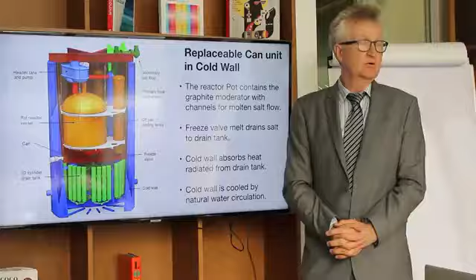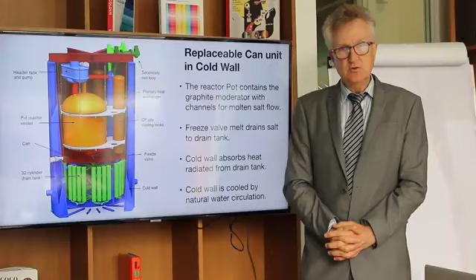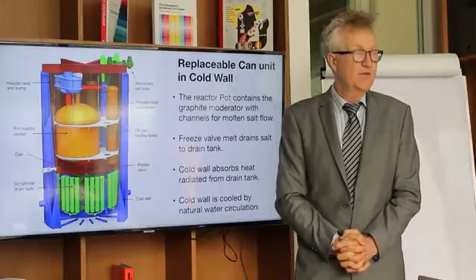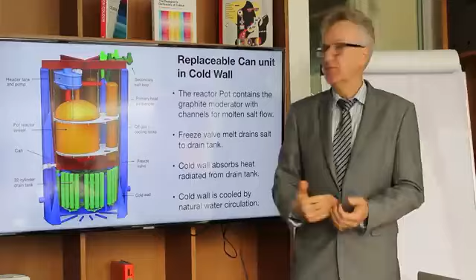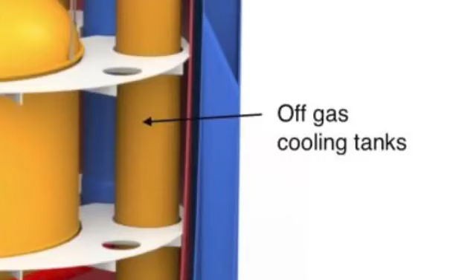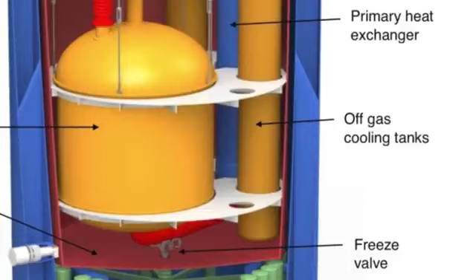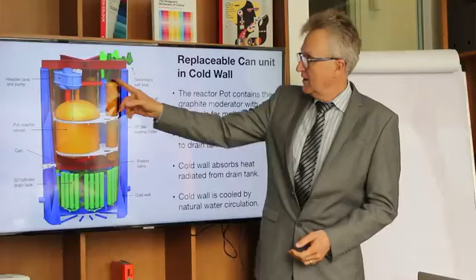A lot of the fission products will become either xenon or krypton. One of the nice things about liquid-fueled reactors is xenon and krypton do not have much solubility in the salt at all. They will bubble out. They're going to come out. So we go ahead and help them come out and then have a sweep gas of helium to push it along into these off-gas tanks where radioactive xenon and krypton can decay away. And after it's decayed for about a week, it'll come out of there and go into additional tanks.